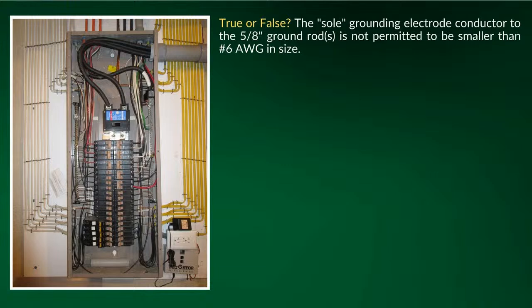The other thing we learned in that podcast was that the table is based off of a multiplier that comes from 250-102C1, and then that's how they got the ratio of what the grounding electrode conductor is supposed to be to the ungrounded conductor on the service entrance. Well, the made electrodes were tested and sized based off that testing, not off the table. So that was one of the things for me that really opened my eyes a lot.